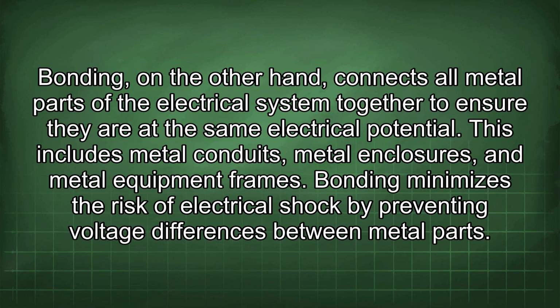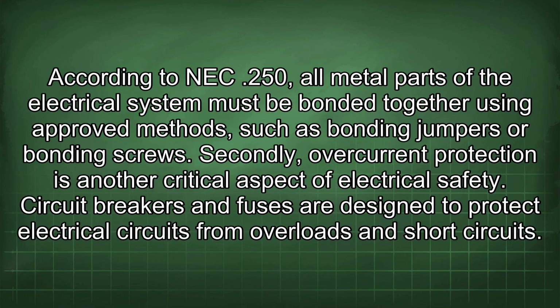Bonding, on the other hand, connects all metal parts of the electrical system together to ensure they are at the same electrical potential. This includes metal conduits, metal enclosures, and metal equipment frames. Bonding minimizes the risk of electrical shock by preventing voltage differences between metal parts. According to NEC 250, all metal parts of the electrical system must be bonded together using approved methods, such as bonding jumpers or bonding screws.